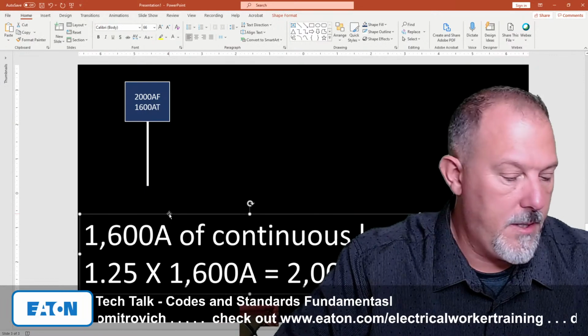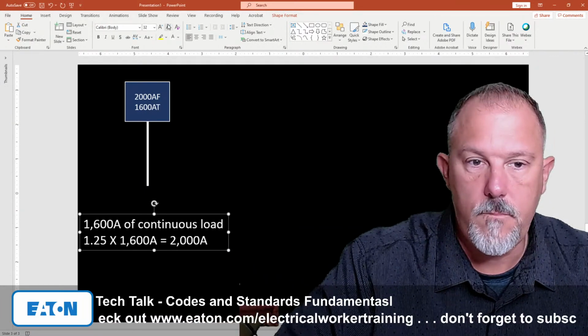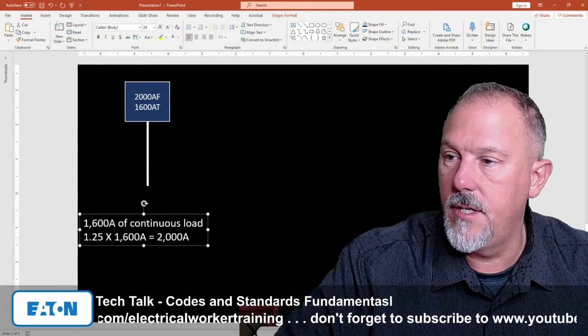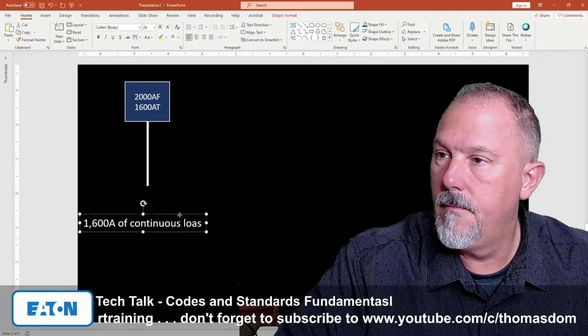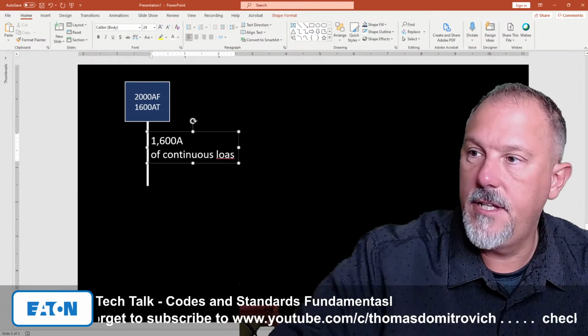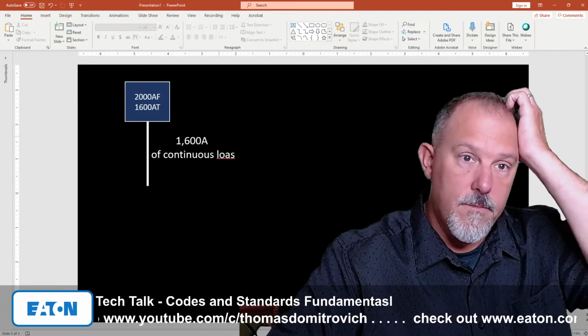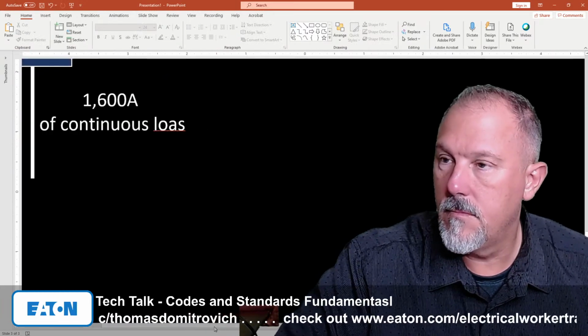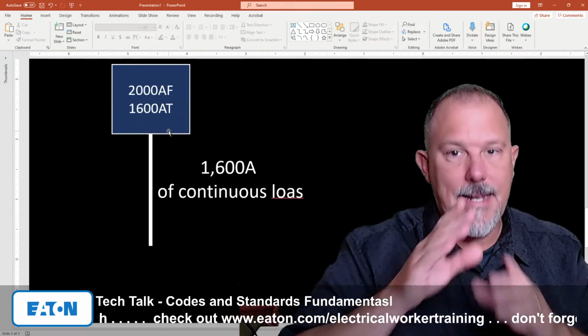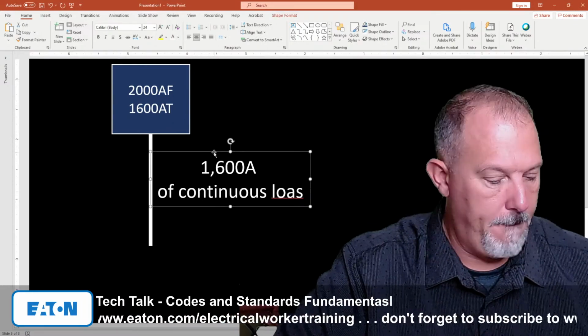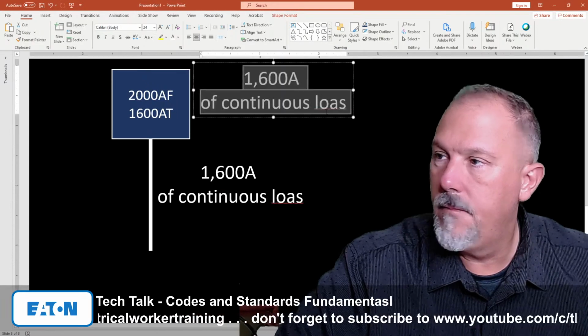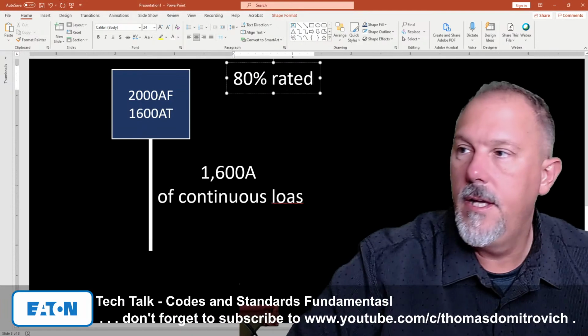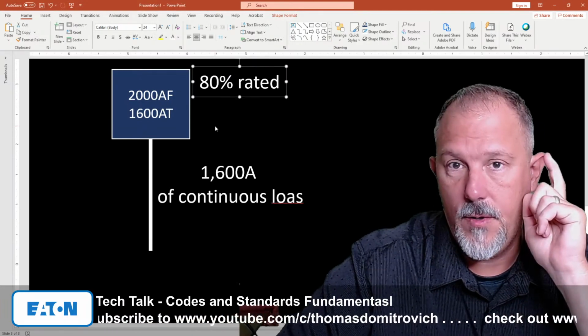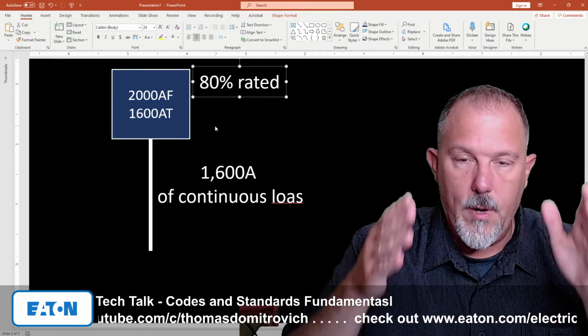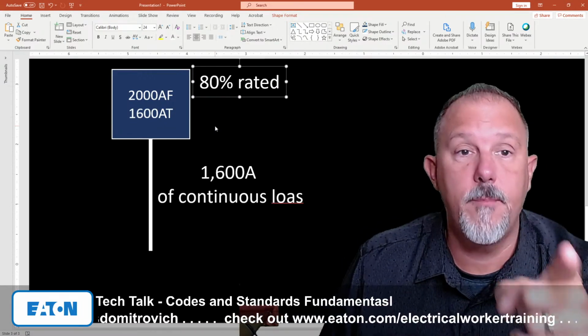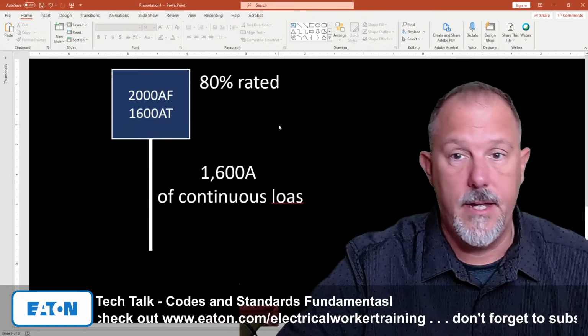And I am going to copy this. Actually, I'm just going to use it again. And I'm going to say 1600 amps of continuous load. Now, the question is, that circuit breaker is an 80% rated circuit breaker. What do we mean by that? Now remember, what does that mean? When I have an 80% rated breaker, this 2000 amp frame circuit breaker, let's talk about how it is tested as per the UL standard.